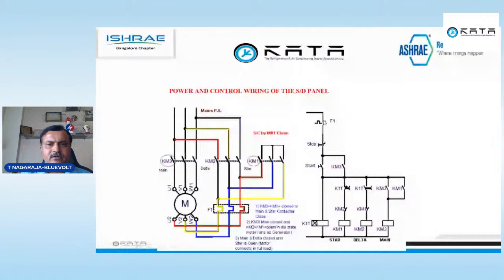This is the control circuit: overload, then stop push button, start push button, then timer. Once the timer NC, then star, KM2. So once the timer is over, this will get NO. Then KM2 will operate. That means delta will switch on. Once delta switches on, this will get open, and your star also gets open. So that will be safety.